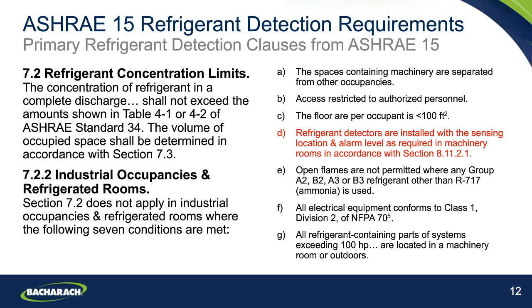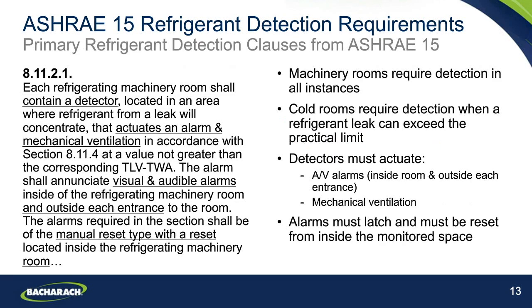So what we can determine here from ASHRAE 15 is that within an industrial occupancy, when it comes to refrigerant detection, we're essentially employing exactly the same parts of the regulations and standards that apply to machinery rooms. So if we look at that part of the standard, this is section 8.11.2.1, which determines here that a refrigerating machinery room shall contain a detector. The language there is important. It is defining a mandate here by use of the word shall. And this detector should actuate an alarm and actuate mechanical ventilation if a leak is detected.